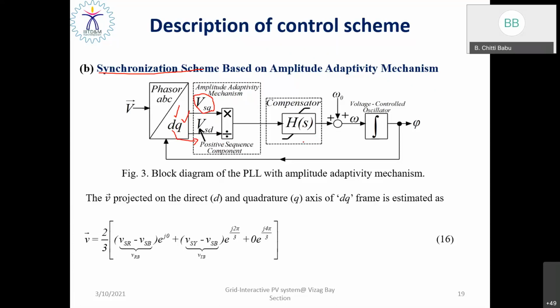Then we are giving it to the compensator based on the proper controller gain, and the error will be generated. Then that can be compared with the natural frequency, what is called the 50 hertz component. We are able to generate the value of omega. That omega can be integrated in order to get the exact phase angle of the utility grid, basically what is called the fundamental phase angle. Then it has to work in a closed loop manner so that it is able to track the fundamental frequency component of the utility grid. This is what is called the phase locked loop.